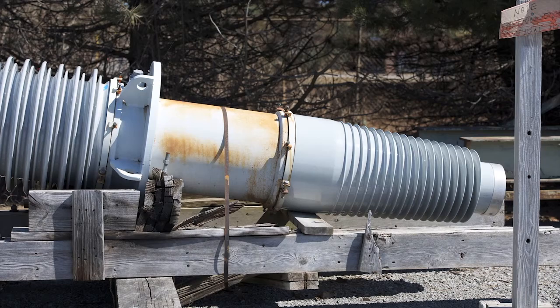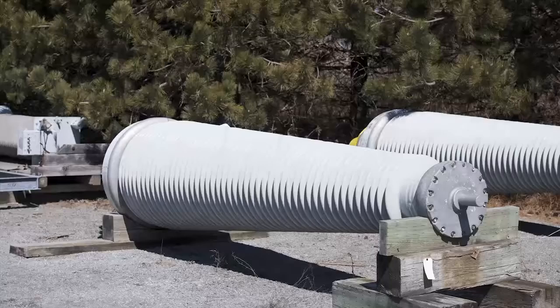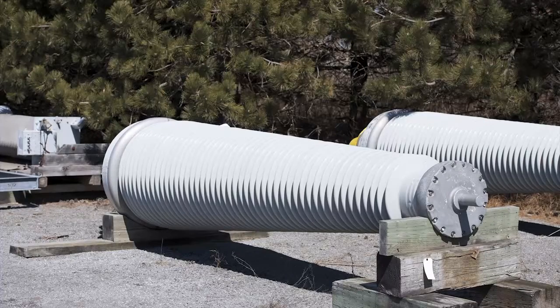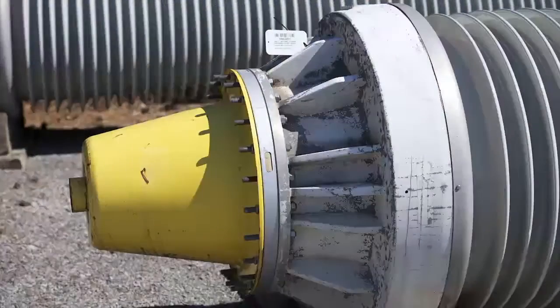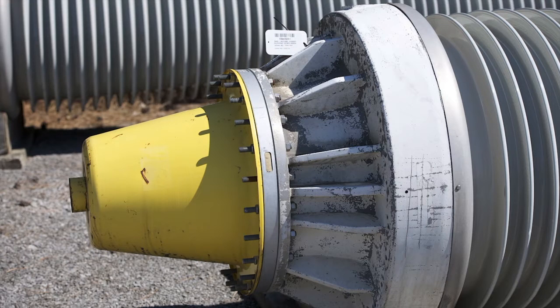By contrast, on field graded bushings, the stress is linearized and spread out over a greater distance, resulting in a greater margin of safety. The impact of this is evident when one looks at a simple 110 kilovolt bushing. With field grading, the diameter of the porcelain housing required for this voltage class is only about 240 millimeters measured across the sheds. To handle the same stresses, an identical ungraded bushing would need a housing with a diameter of 475 millimeters, virtually double the size.